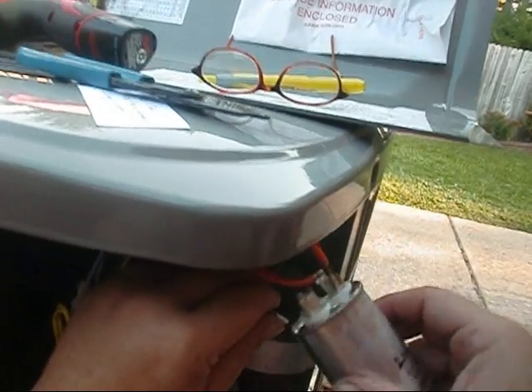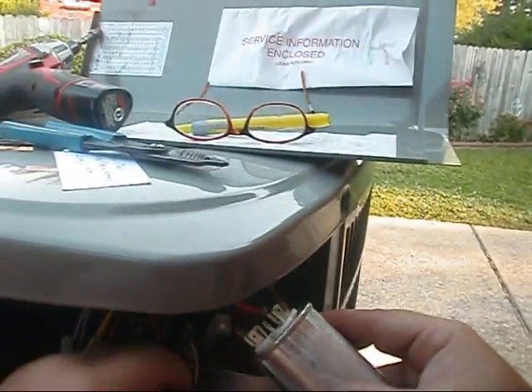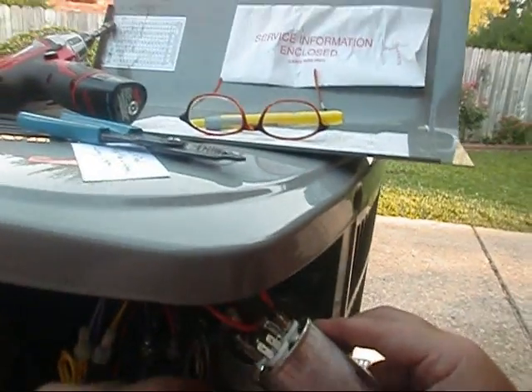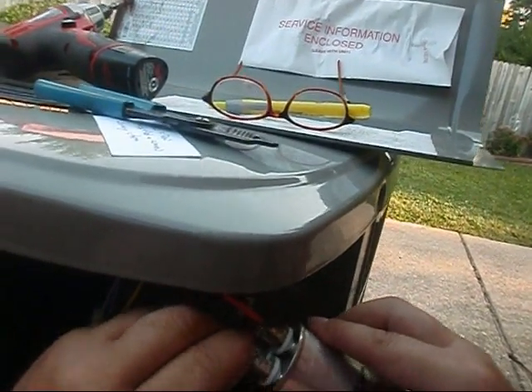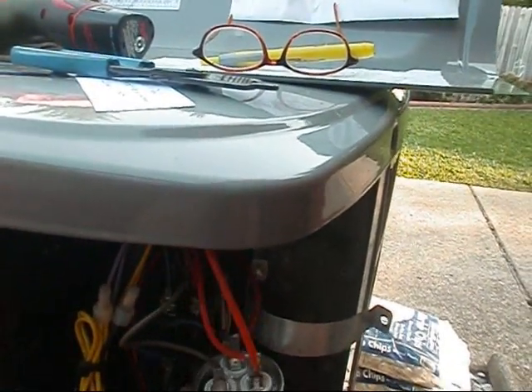And our red, which will be common. And where's our purple — that's going to be common. And our brown is going to be fan. I just want to test it real quick. I just went in and kicked the thermostat — she just engaged. You can actually see the contactor where she's pulled in. And I got my green light.